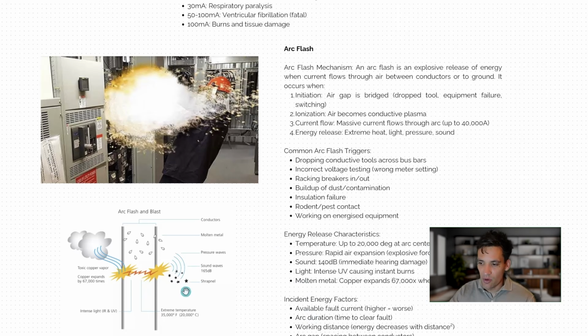So when an arc forms, what happens? Well, first, huge temperatures develop in the arc center, around 20,000 degrees Celsius. There's a huge expansion of air, which causes an explosive force, which is why you hear the very loud clap of thunder when there's a lightning strike. You get very intense light and strong UV, which can cause instant burns. And you also get some molten metal when the conductors actually expand and can vaporize. That's why when you see a failed electrical circuit, there's always burning or some sort of molten metal.